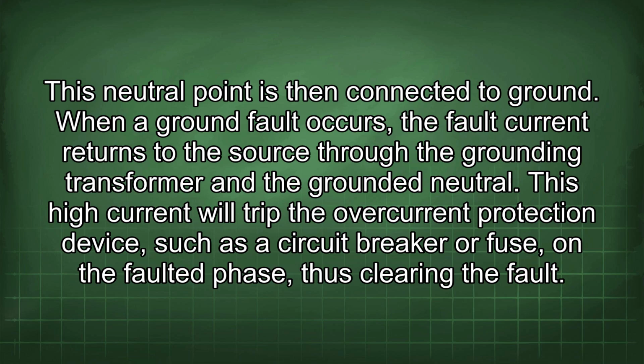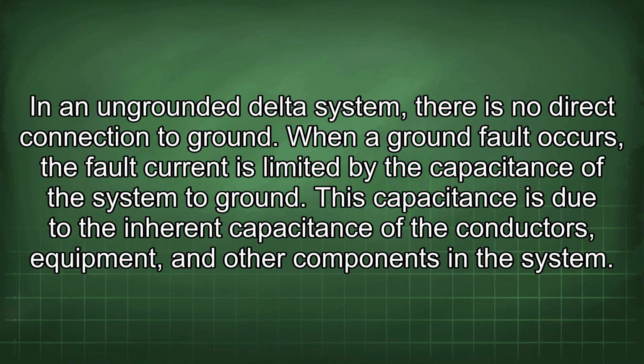When a ground fault occurs, the fault current returns to the source through the grounding transformer and the grounded neutral. This high current will trip the overcurrent protection device, such as a circuit breaker or fuse, on the faulted phase, thus clearing the fault. In an ungrounded delta system, there is no direct connection to ground. When a ground fault occurs, the fault current is limited by the capacitance of the system to ground.